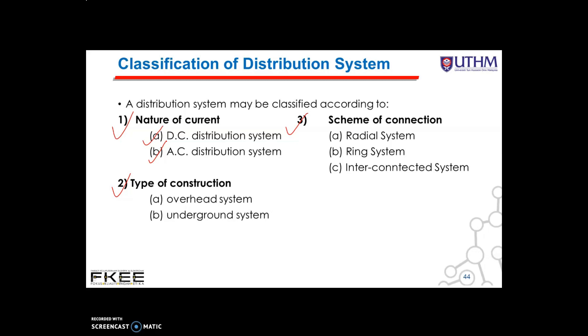The second classification is the type of construction. According to type of construction, the distribution system may be classified as: A, the overhead system, and B, the underground system. The overhead system is generally employed as it is 5 to 10 times cheaper than the equivalent underground system. In general, the underground system is used at places where overhead construction is impracticable or prohibited by local laws.